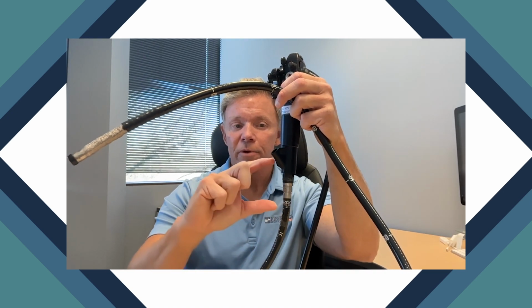We've seen a common area for these tubes to kink at the top of the insertion tube, right before it leads into the body. During a procedure, the physician holds the control handle, manipulating the knobs while also maneuvering the scope back and forth to navigate through the colon. This puts a lot of pressure on the insertion tube before it connects into the control body. Often when you see scopes hanging in the closet, you might see kinks or buckles at the top of the insertion tube, right below the boot before it enters the body. That's a sign the outer tube is wearing, breaking down, and kinked. These dents, crushes, and buckles will eventually affect the inner components of the scope too.